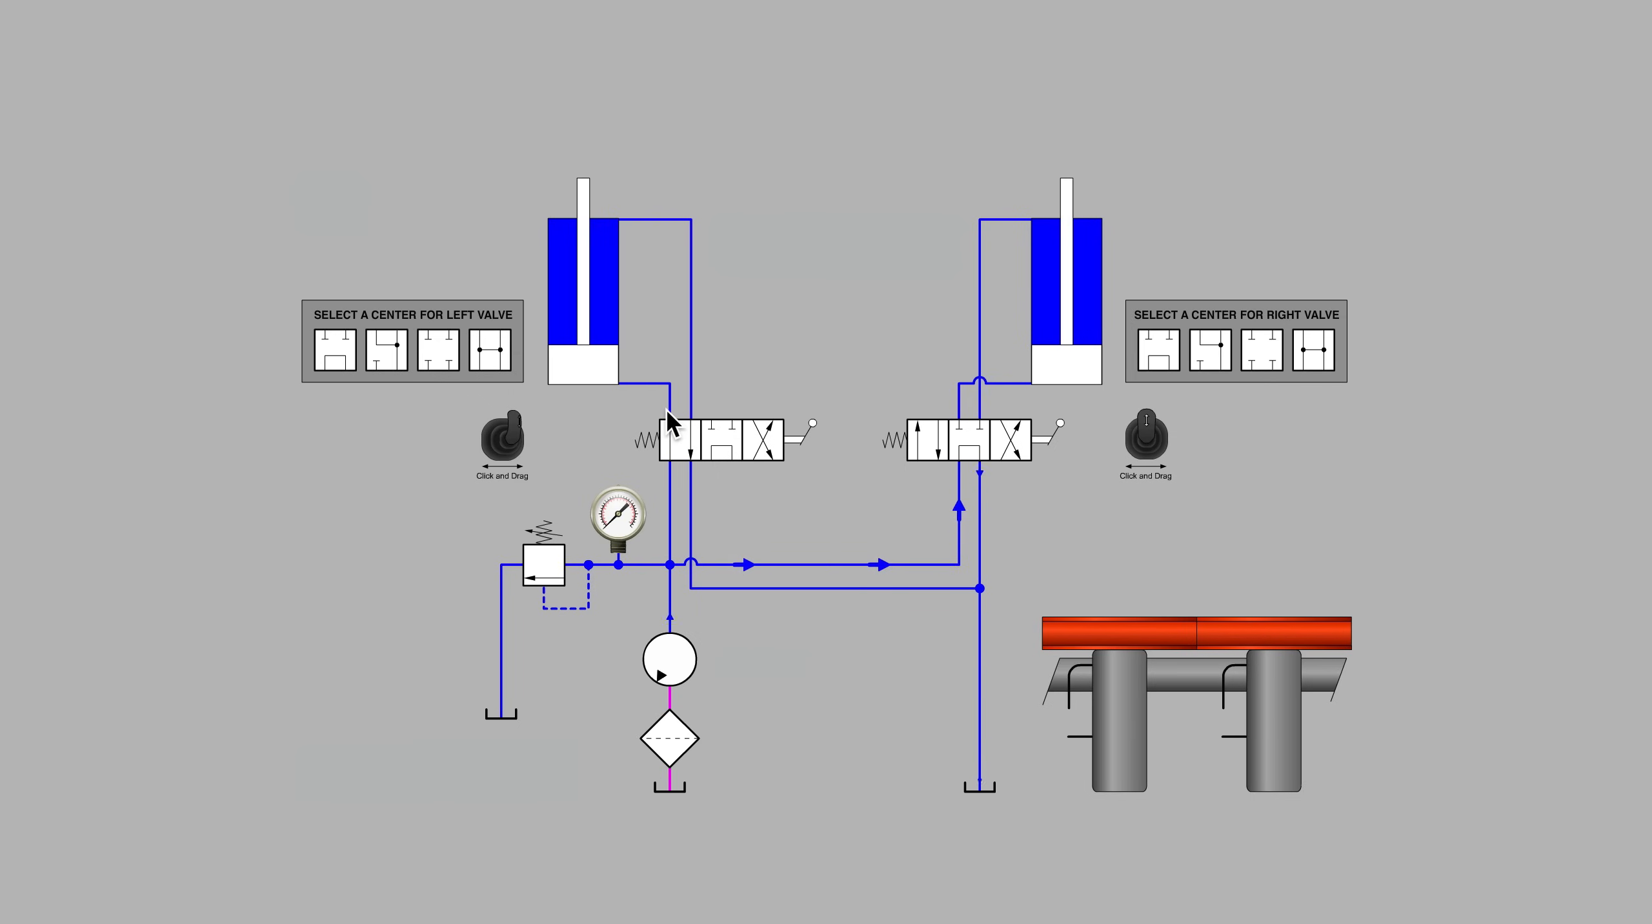Just like as we were working with the open center valves, while trying to extend the cylinder on the left, all of the pumps flow has a leakage path back to tank through the valve on the right. Same holds true for the other direction. Perhaps if we were to introduce a valve on the right that blocks the P port. In this particular case, I've chosen the float center. What will happen now?